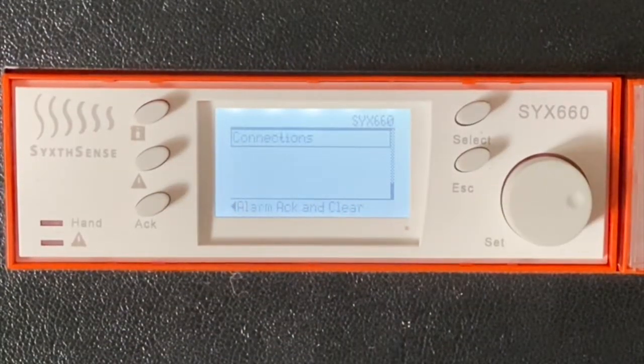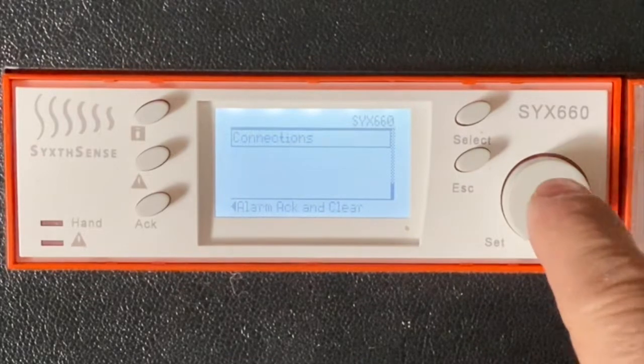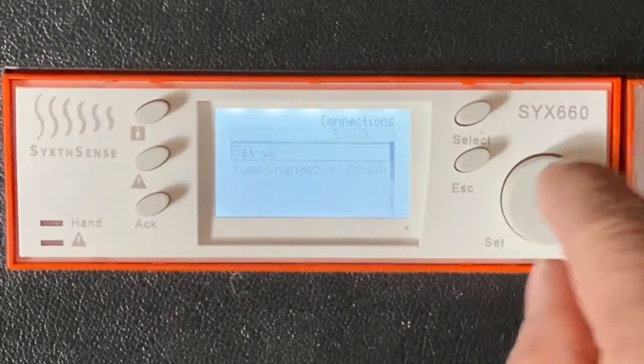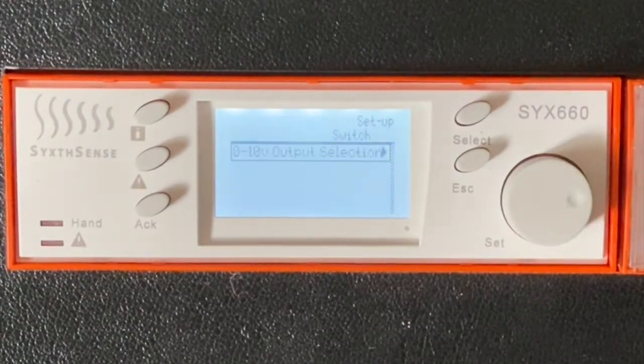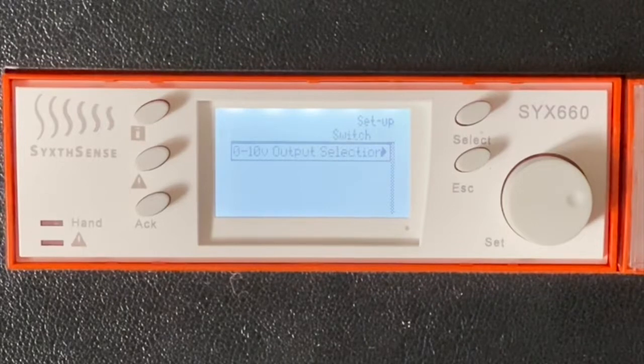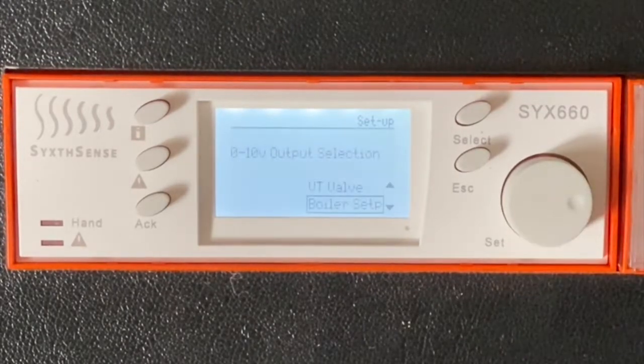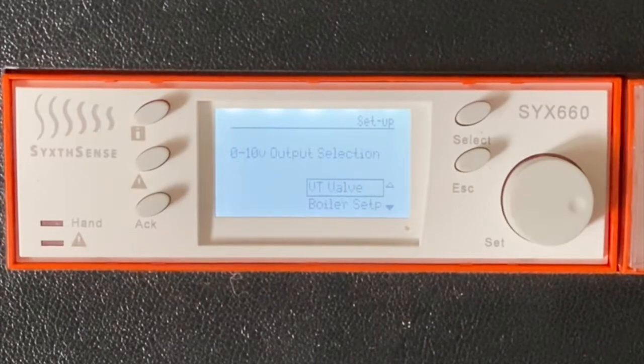Finally, we can set up the last option called connections. Press the wheel on connections and choose switch, and we choose setup. This is where we set up the use of the 0 to 10 volt output that the SYX controllers offer. There are three options. The first option is whether we use it for controlling the variable temperature valve as a 0 to 10 volt signal. The controller naturally offers a drive open or a drive close signal, which is the majority of products on the market that the SYX replaces.